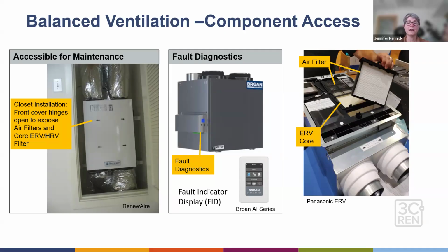A lot of the systems now are coming up with the fault diagnostics, and they have their fault indicator display so that you would mount that display so that it would alert you and warn you, and you could see it if something is not functioning properly. And also it reminds you when it's time to change air filters or do maintenance on the ERV core.